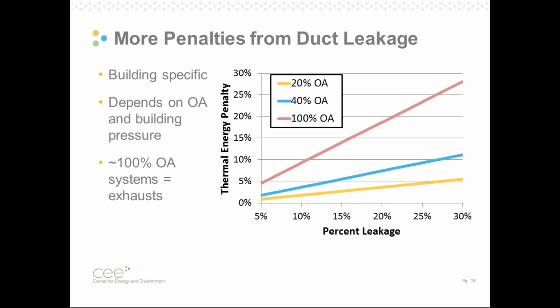For example, a regular supply system in a ceiling return plenum might have typical outside air fractions somewhere between 20 and 40%. At 10% duct leakage, we're seeing somewhere around 2 to 8% of lost thermal energy. So 2 to 8% of the energy put into your flow from a heating coil is essentially being evacuated out the building without doing anything for us. In Minnesota, that's a really big deal. We have a very high heating load. The situation is even more extreme in 100% outside air systems and or exhaust systems, where we essentially have a nearly 1-to-1 ratio of leaked CFM with lost thermal energy.